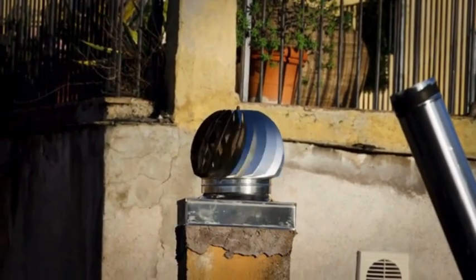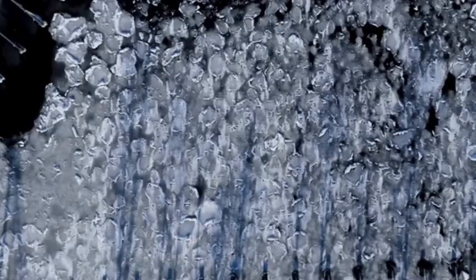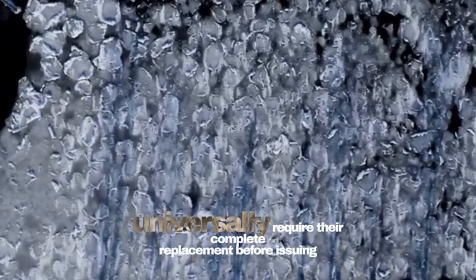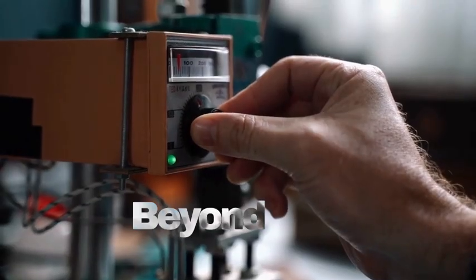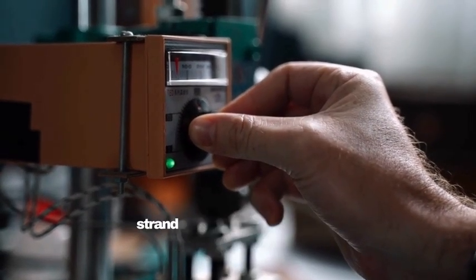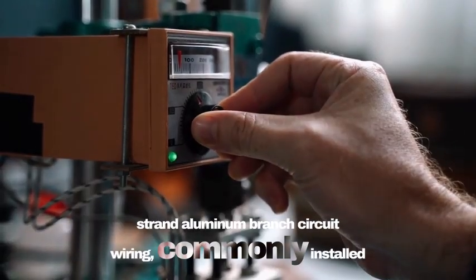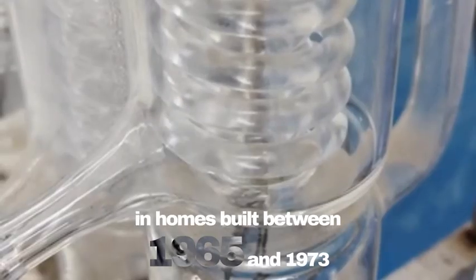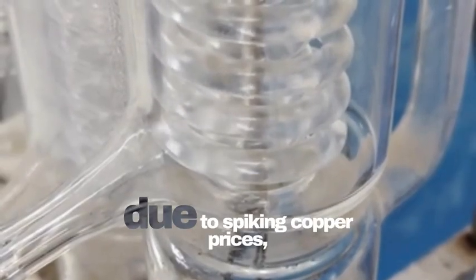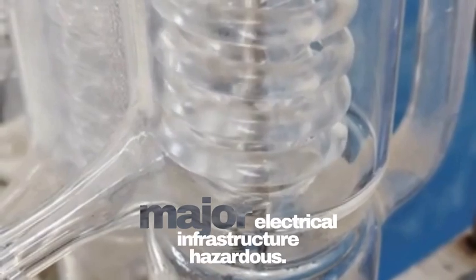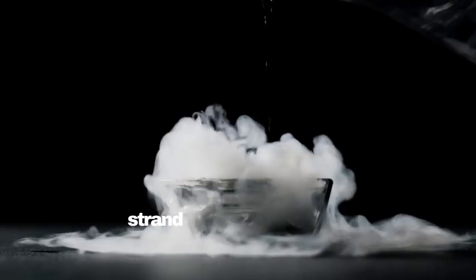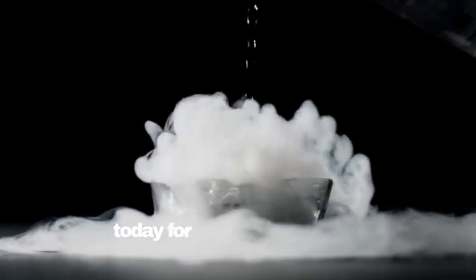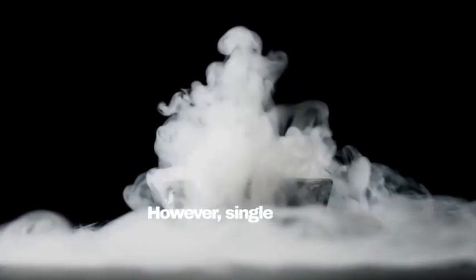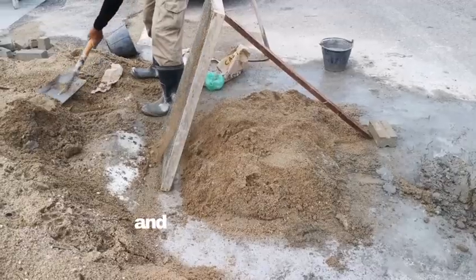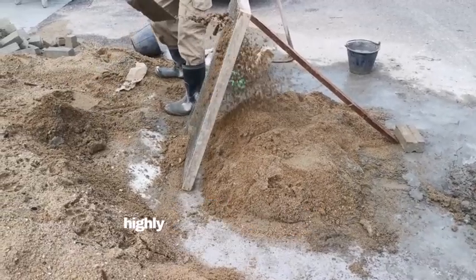Properties with FPE or Zinsco panels are flagged by insurance companies as high risk, and carriers will almost universally require their complete replacement before issuing a standard homeowner's insurance policy. Beyond defective panels, the presence of single-strand aluminum branch circuit wiring, commonly installed in homes built between 1965 and 1973 due to spiking copper prices, represents a major electrical infrastructure hazard. It is vital to note that multi-strand aluminum wiring is still safely used today for main service feeder lines.